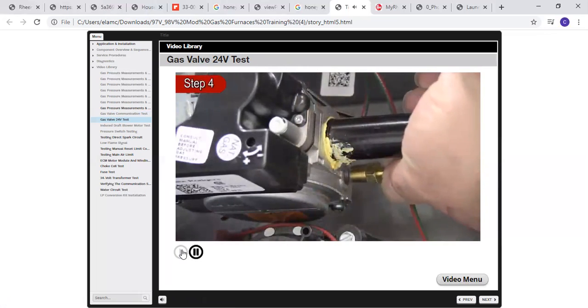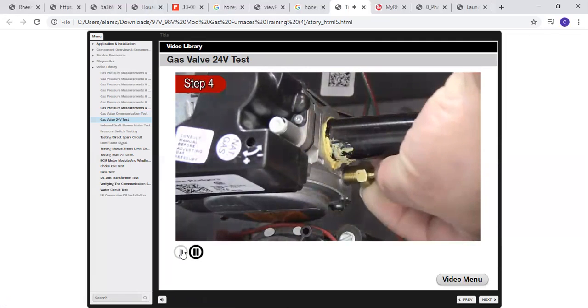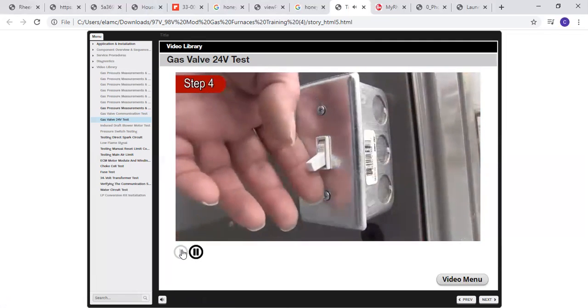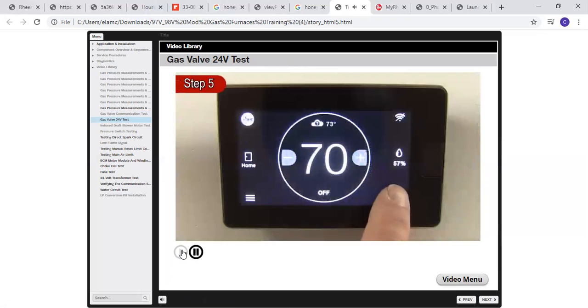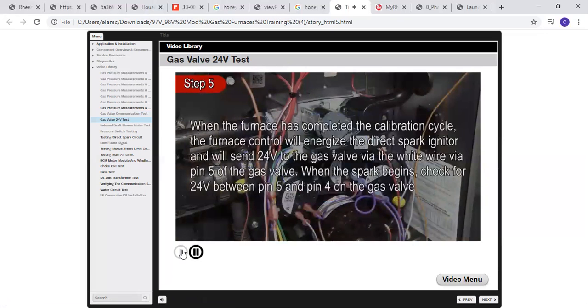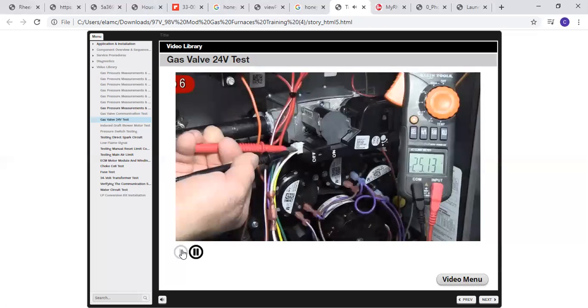Step 4. Connect the gas manometer to the outlet pressure port on the gas valve and restore power to the furnace. Step 5. Call for heat. When the furnace has completed the calibration cycle, the furnace control will energize the direct spark igniter and will send 24 volts to the gas valve via the white wire via pin 5 of the gas valve. When the spark begins, check for 24 volts between pin 5 and pin 4 on the gas valve.